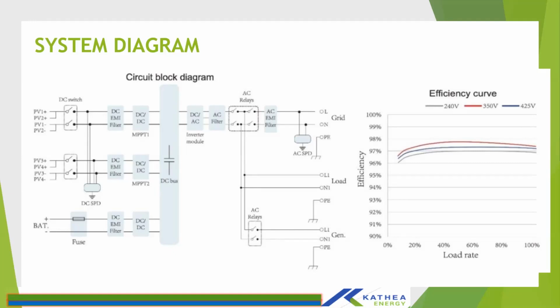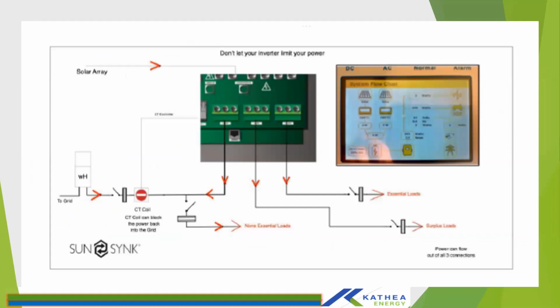The flow chart of power inside the inverter. So the wiring diagram for the system: you would have your PV array wired to the inverter, to the PV input points, and then you would have your grid in. So as I've said, the system is a pure hybrid. You need to utilize all the PV to your loads, both critical and non-critical.